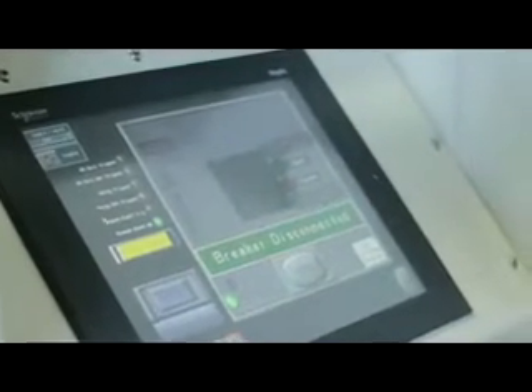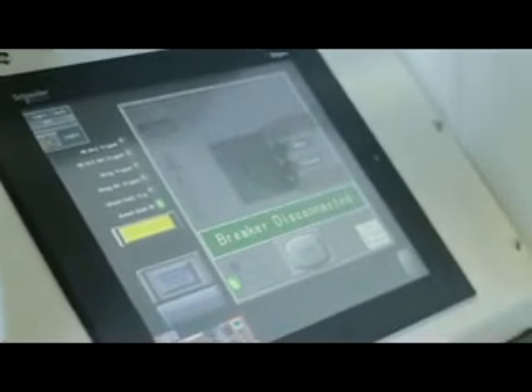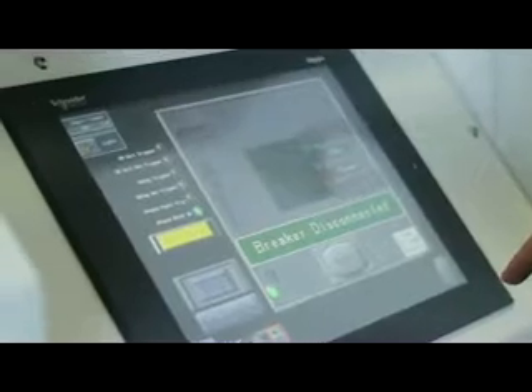And once we hit that operation button, the open and close, the breaker automatically racks in or racks out so that all the current carrying contacts are disengaged off of the stationary contacts, so there's zero incident energy on the breaker when you apply your safety padlock.